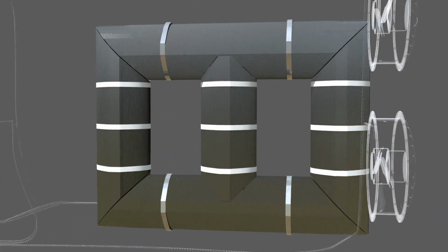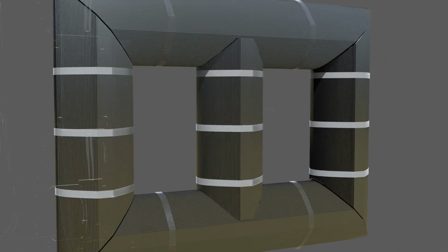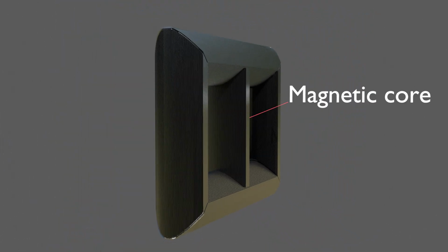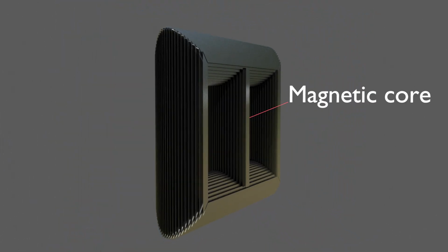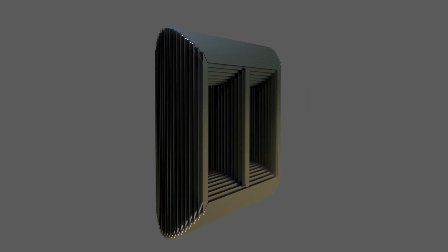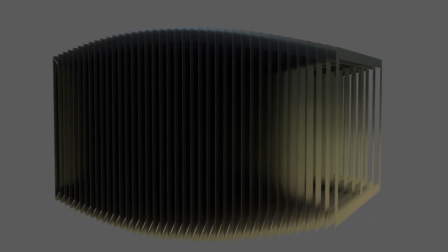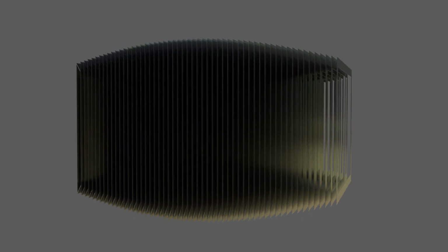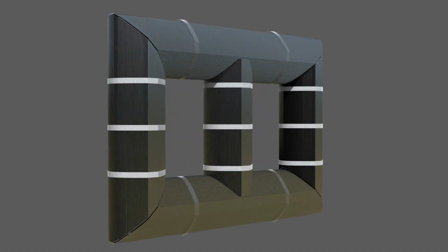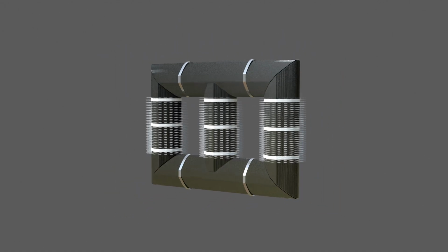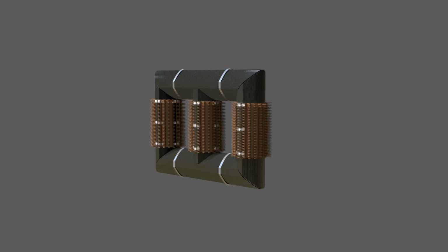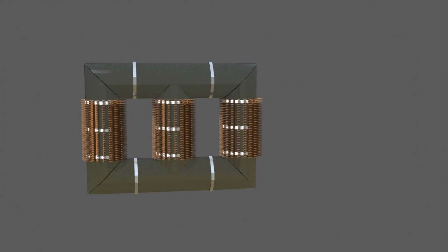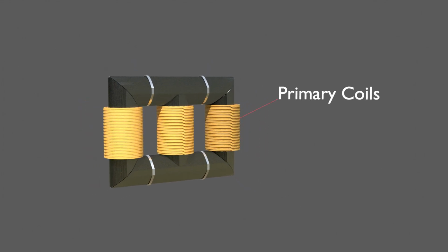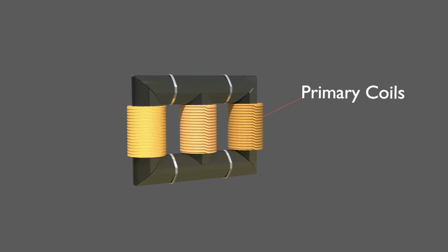A well-designed core improves transformer efficiency and minimizes heat generation, ensuring reliable performance. The magnetic core of a power transformer is made of thin laminated steel sheets, designed to reduce energy losses due to eddy currents. It provides a low-reluctance path for the magnetic flux, allowing efficient transfer of energy between the primary and secondary windings. The primary winding is carefully wrapped around the magnetic core, in a circular shape.